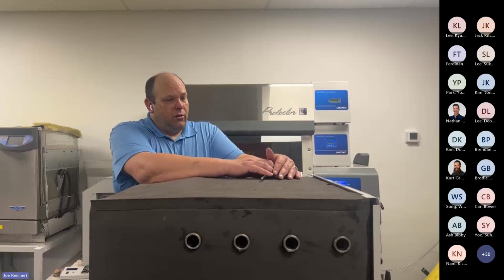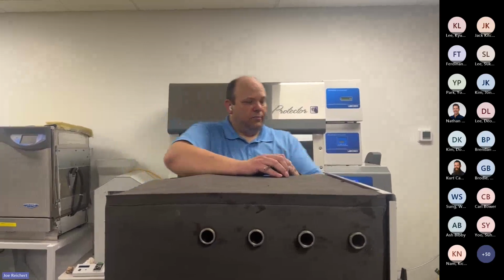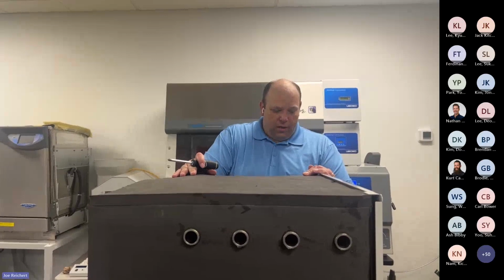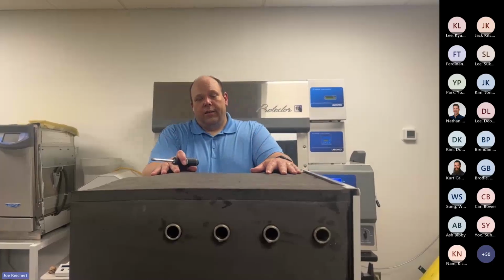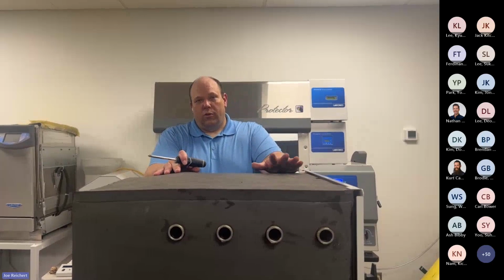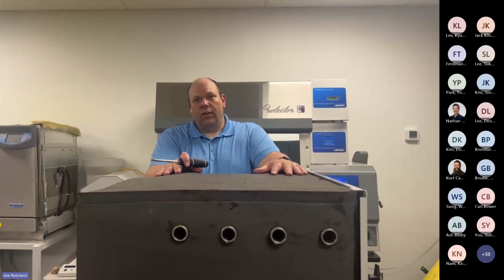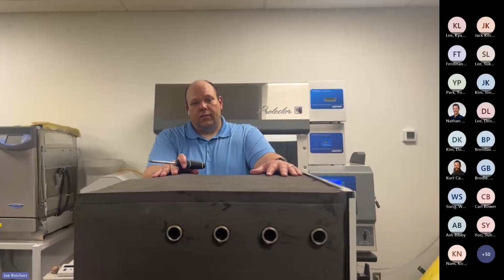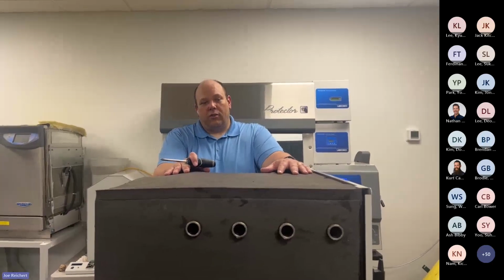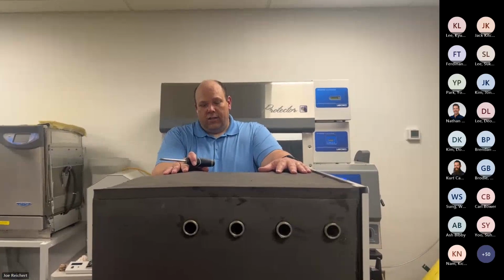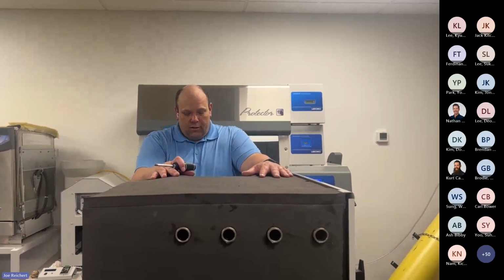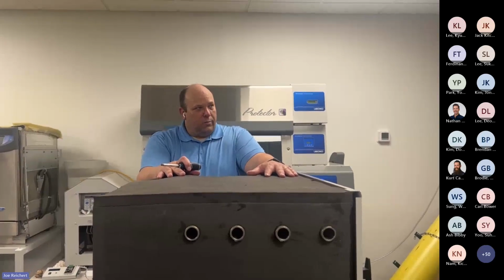However, we still left that IQ/OQ on there to give us a little wiggle, a little cushion there on the time on trying to make temperature on the shelves, because there's a lot of environmental conditions that can change within our labs. Some places that don't have as good air conditioning, these units will not work great in a room that is hot. So if it's over 23 C, if you start getting into a room that's 25 to 30 C, the unit is not going to function as well as it should, because it can't remove all. Now it's having to dry your samples and hold a load there, and it's also holding a load from the room, is how hot it is. It can't remove the heat. So make sure your rooms are good and cool to be able to operate them very good.